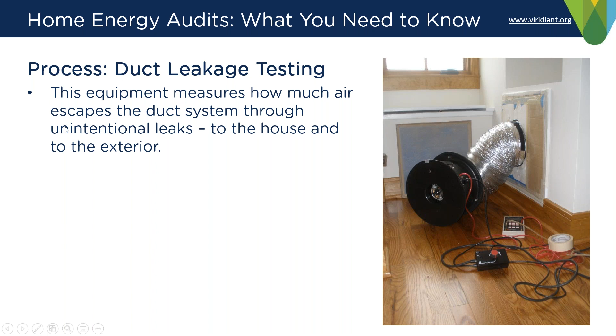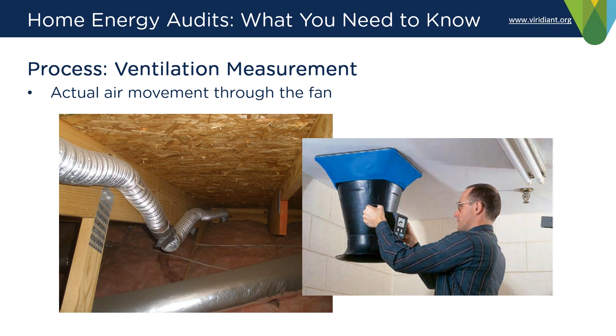Big opportunity. We don't do this test often, but sometimes a lot of people find that their ventilation fans aren't really doing anything. We can measure that using this flow hood there on the right, to see when it's running how much air it actually moves. The fan could be rated for 50 cubic feet per minute, and often it'll be moving less than 20, in part because the duct that the fan is trying to push air into is so twisty, turny, crushed and long that it just can't move the air through.